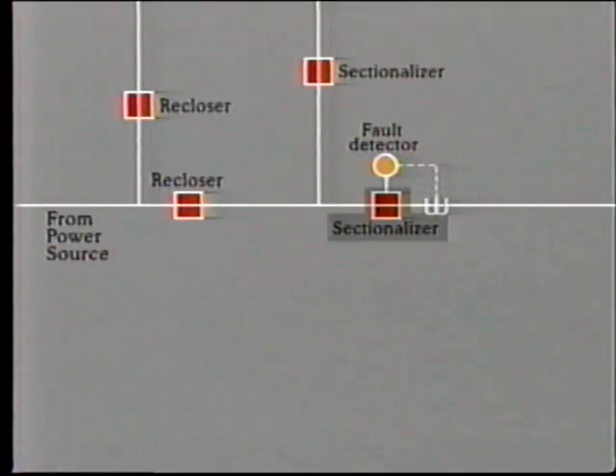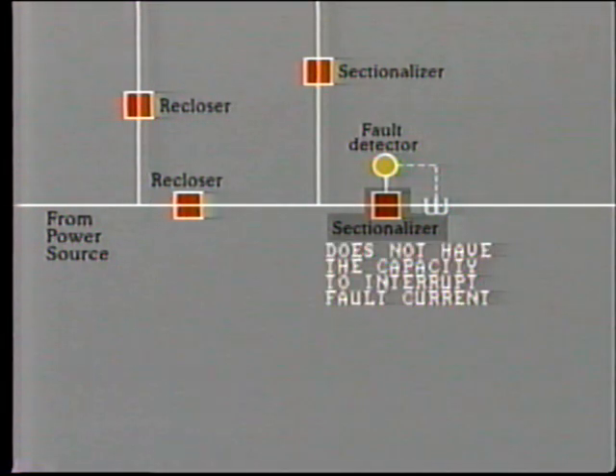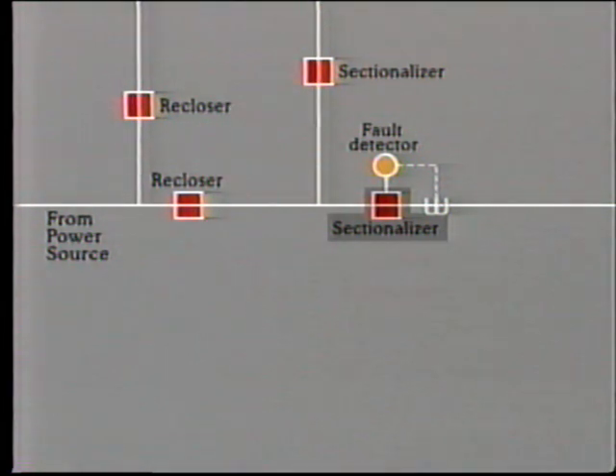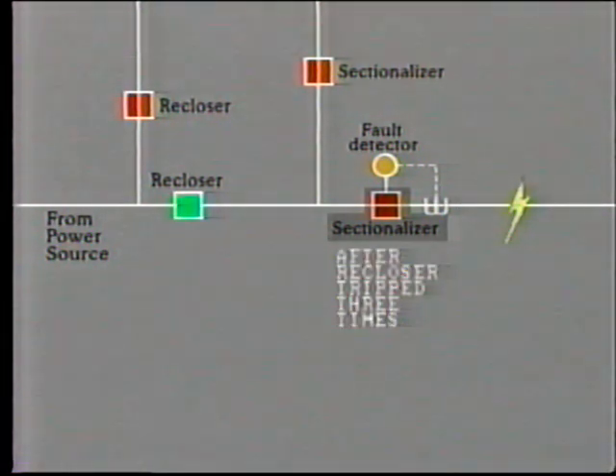Right now, let's move on to look at another example of logic, this time on a distribution feeder. This sectionalizer is located downstream of the recloser. The sectionalizer does not have sufficient capacity to interrupt fault currents. Instead, it is used to open and so clear a faulty circuit once the line is dead, that is, after the recloser has tripped the third time.